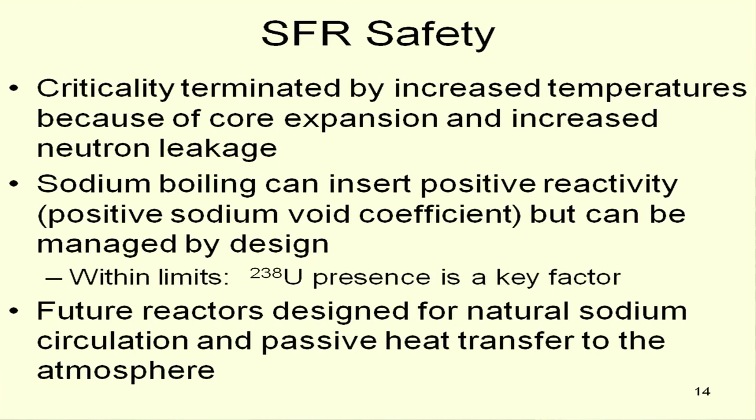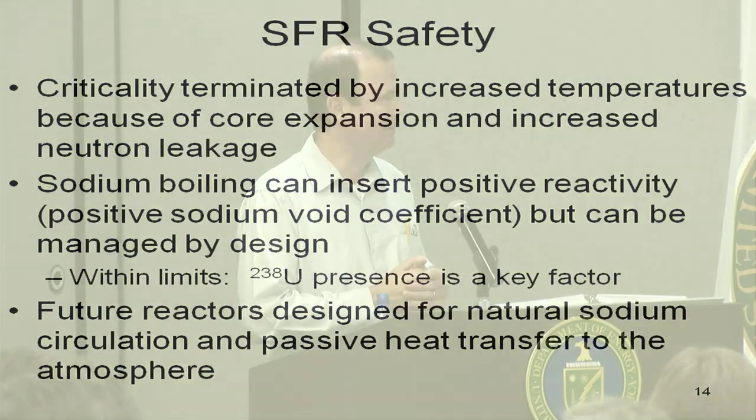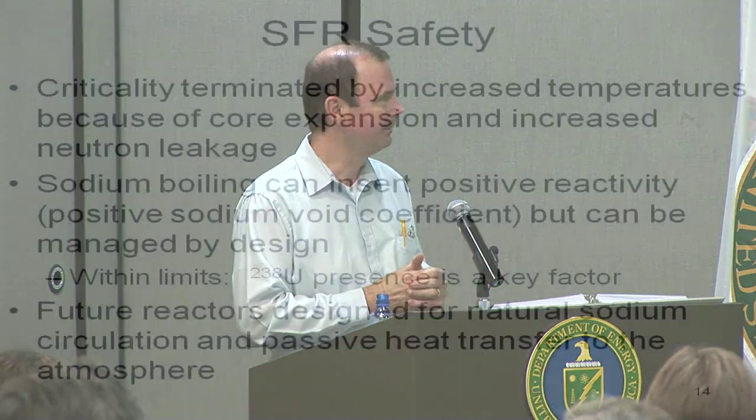For the safety, criticality, as with some others, is terminated by increased temperatures because of core expansion and the consequent more neutron leakage. Sodium boiling can insert positive reactivity, which means whereas boiling, say, water in a boiling water reactor is negative reactivity, it tends to want to shut it down because of the moderation. The sodium removes some neutron capture, and actually the spectrum can be harder and faster at that point. So it can want to sort of get away from you. This can be managed in most reactors by design. In other words, fix it so you don't have this positive sodium void coefficient. But there are limits to it, and having U-238 in there is a key presence because of the Doppler broadening and increased capture with temperature in those resonances.